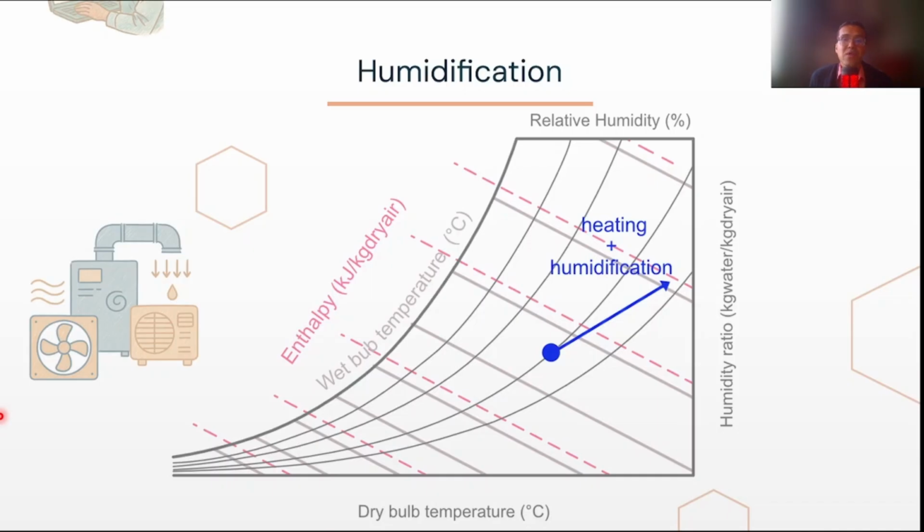Spray humidifiers, which add water vapor with less thermal input, are often found in greenhouses where temperature must be tightly controlled. In HVAC design, we typically focus on humidification processes that also increase the air temperature, such as steam injection, because they are more compatible with thermal comfort goals. While it is technically possible to humidify by spraying cool water, which can lower dry bulb temperature, this is rarely desirable in most building applications.